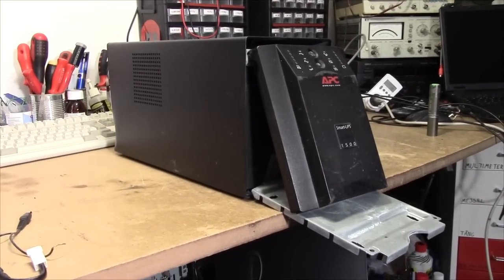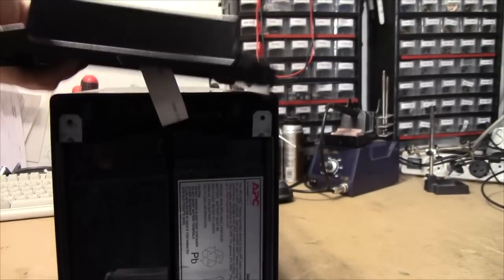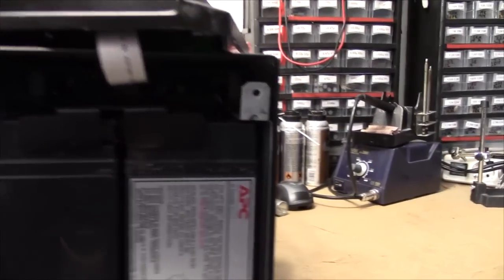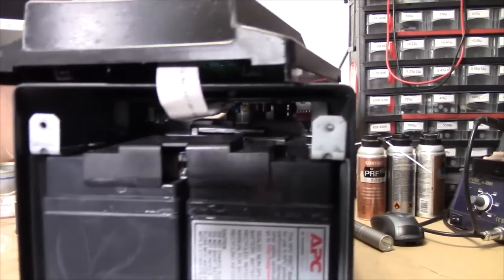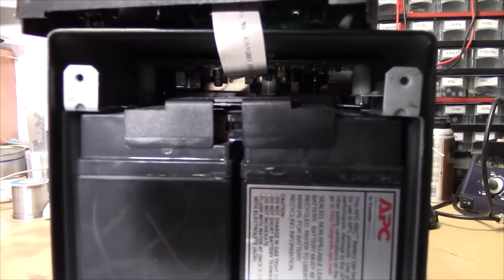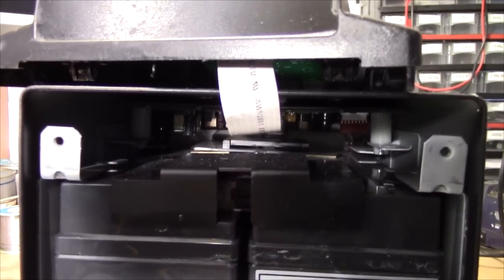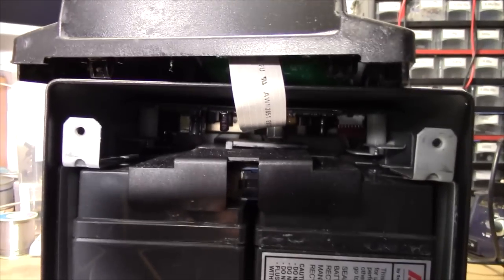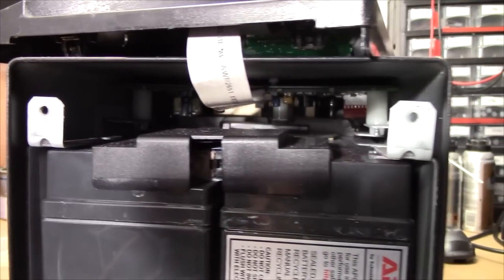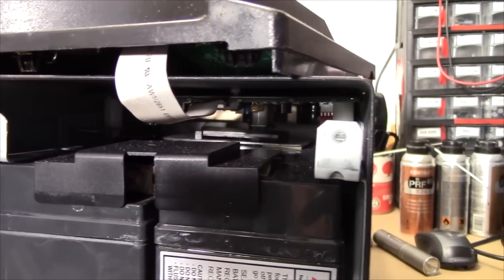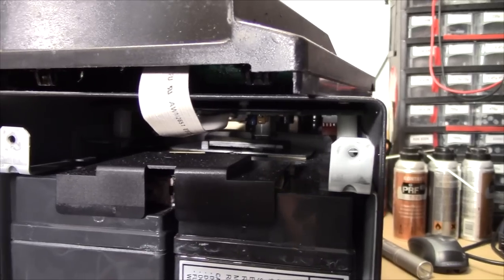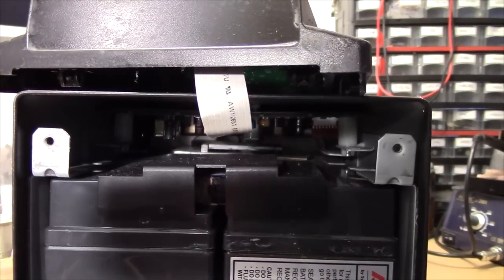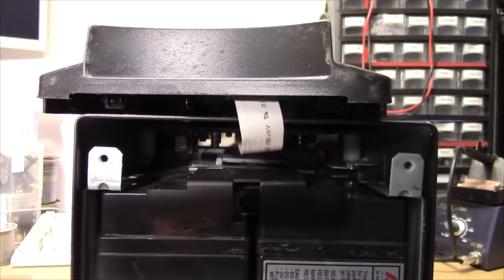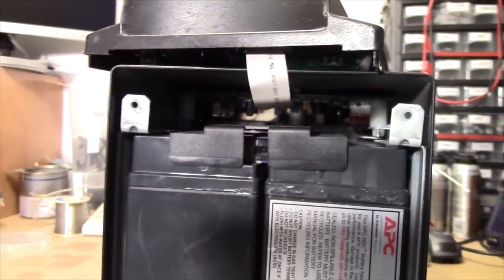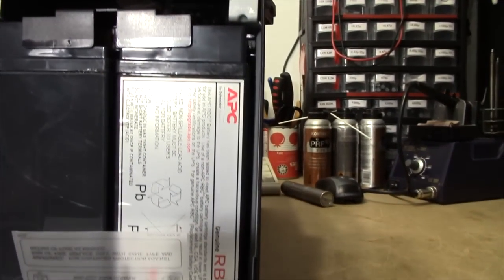It's not a real APC UPS unit unless the battery's swollen up. And I just thought I'd show everybody this fairly extreme one that I got a while back, where the batteries have actually swollen so much that the covers for the terminals have...